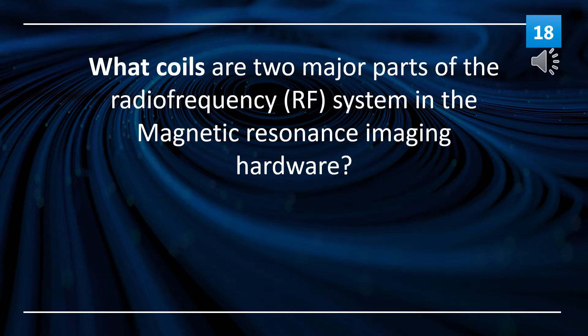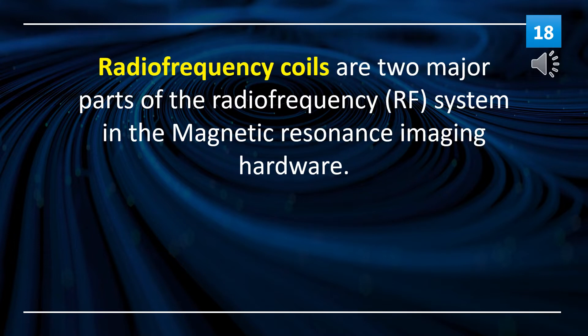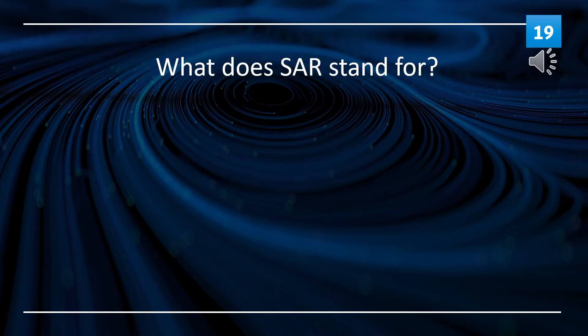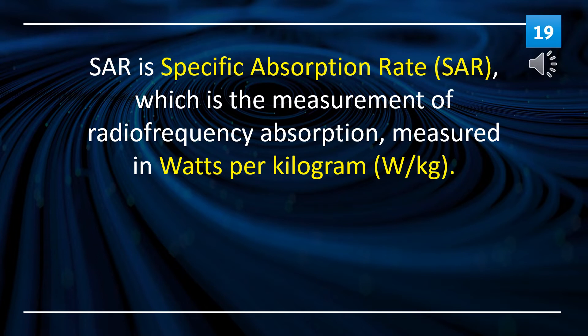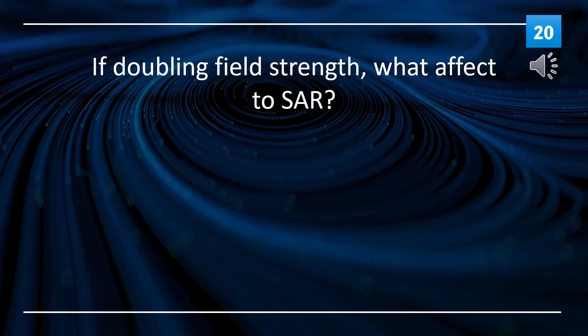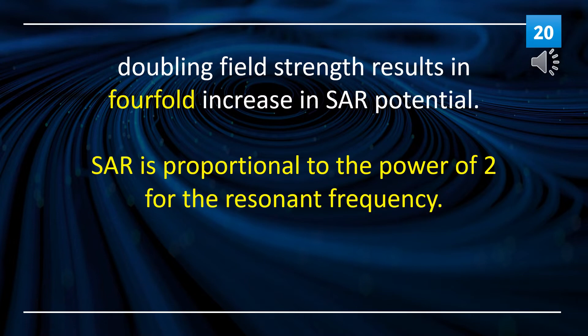What are the two major parts of the radio frequency system in MRI hardware? Radio frequency coils are the two major parts. SAR stands for specific absorption rate, which is the measurement of radio frequency absorption, measured in watts per kilogram. Doubling field strength results in a four-fold increase in SAR potential — SAR is proportional to the power of 2 for the resonant frequency.